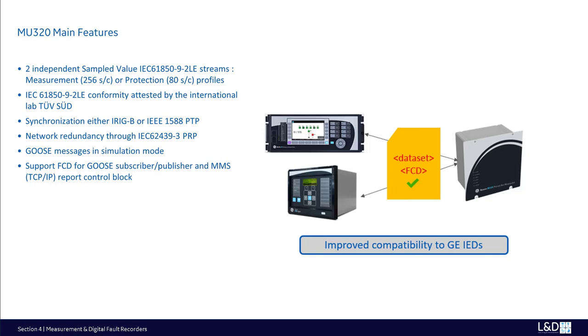MU320 was tested and approved by global testing and certification company TÜV-SÜD according to the implementation guideline for digital interface to instrument transformers. It can be synchronized with either IRIG-B or IEEE 1588 PTP. There is optional PRP function for network redundancy. Goose messages can be in simulation mode, and possible configuration mode are test, test block, off, and on. Alarm LEDs turn orange when MU320 is in the test or test block mode. After rebooting, the MU320 will remain in the test mode.